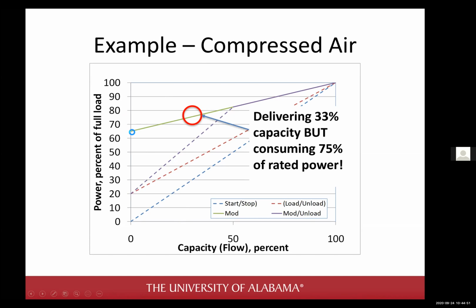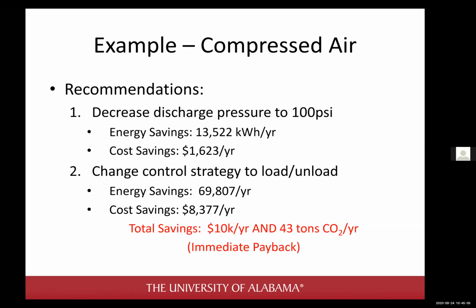Now, we analyzed the system, and we said, okay, here are 2 recommendations we're going to make for your 100 horsepower compressor. We told them to decrease the pressure to 100 psi, which they said they could do because they didn't have any equipment that needed really high pressure. So they decreased their discharge pressure to 100 psi, which saved them $1,600 a year and change, which again is something that's very easy for you to do.